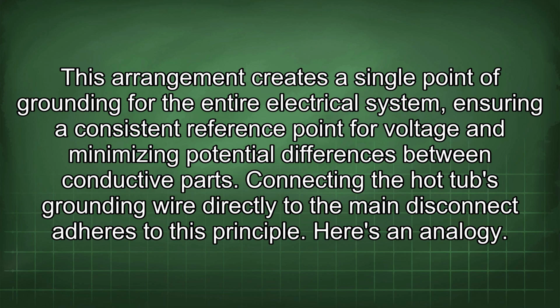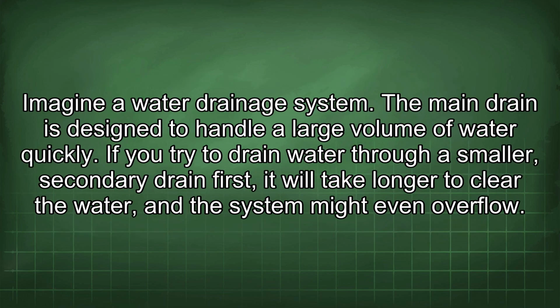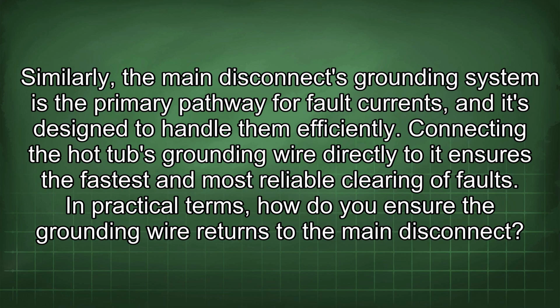Here's an analogy. Imagine a water drainage system. The main drain is designed to handle a large volume of water quickly. If you try to drain water through a smaller, secondary drain first, it will take longer to clear the water, and the system might even overflow. Similarly, the main disconnect's grounding system is the primary pathway for fault currents, and it's designed to handle them efficiently. Connecting the hot tub's grounding wire directly to it ensures the fastest and most reliable clearing of faults.